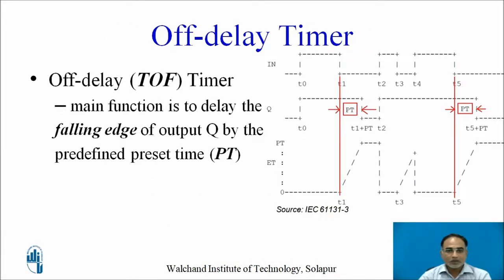Let us learn the operation of the off delay timer with the help of the waveform shown on the slide. The main function of the off delay timer is to delay the falling edge of output Q by a predefined preset time. At t1, input changes from 1 to 0, and after PT duration, output changes from 1 to 0. So a delay of PT value is added between the falling edge of input and the falling edge of output.